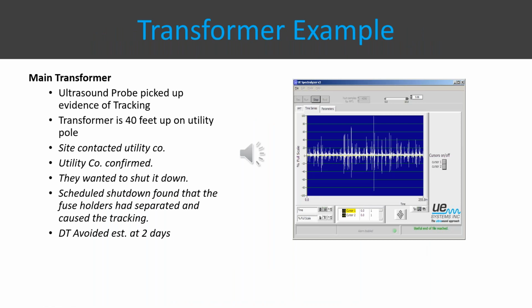Another transformer example, up on a utility pole. This was a situation at a beverage company where, during a routine ultrasound inspection, they picked up some popping and crackling on a transformer and contacted the utility company. They wanted to shut it down, but instead scheduled a shutdown. Fuse holders had separated, causing all the tracking. They estimated that if they'd let that go and the transformer had blown up, it would have been a 2-day downtime event. So again, from a reliability standpoint, it pays to do these simple, easy, safe inspections from a distance on assets outside your facility.